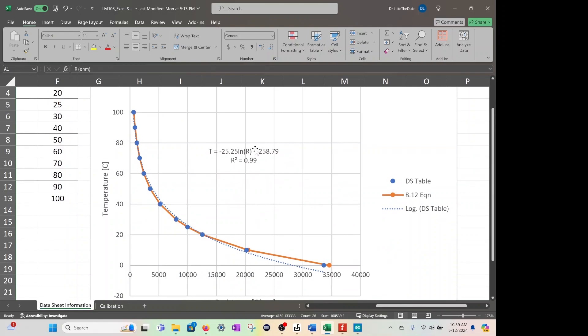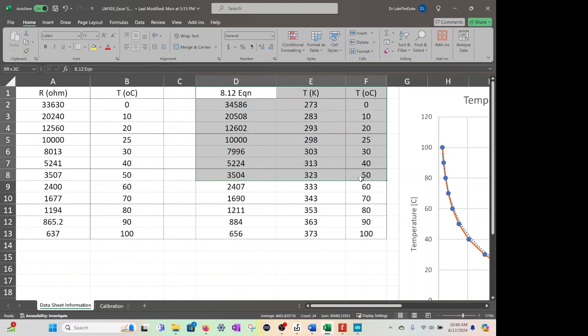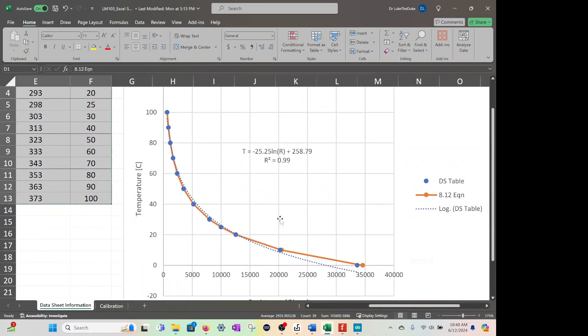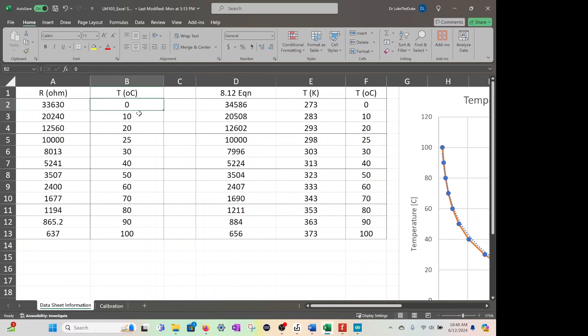So in summary: I used the data sheet values and plotted them, used equation 8.12 and overlaid it, then fit a curve to the data sheet points so I have an equation for any resistance value. During the experiment, temperatures won't be exact integers — you'll get R values in between — so you need an equation that converts any resistance into temperature.